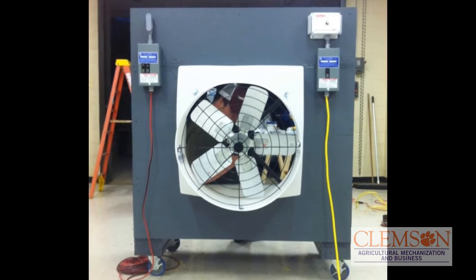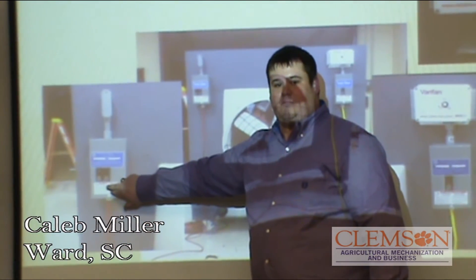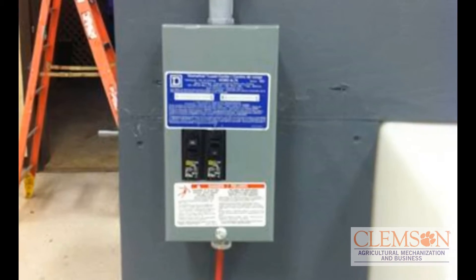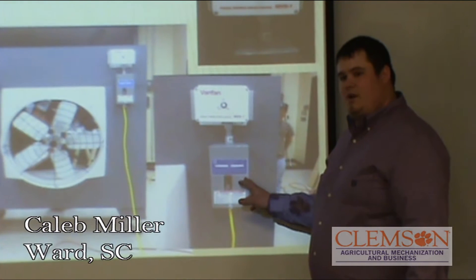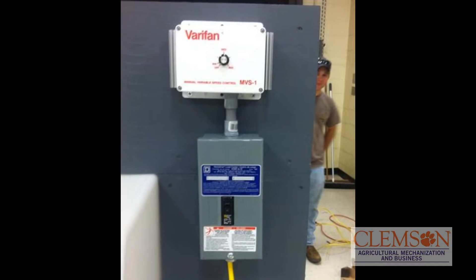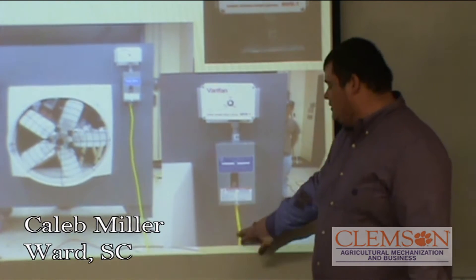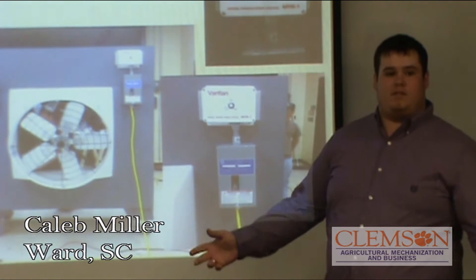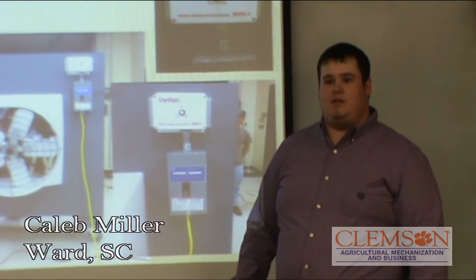This is our largest fan. Our smaller fans run off of this circuit box — we have two 15-amp breakers, each on separate circuits, drawing about four amps total. This is our largest fan circuit box, drawing about three amps running, giving us about seven total running amps. This is a voltage regulator. We put in two complete circuits so we can plug them into two different circuits in the building so that when we start up the fans, we won't trip any breakers.